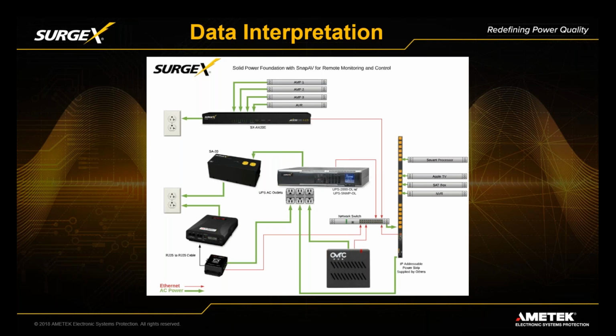And most of the summaries we give back to the integrator revolve around, let's try to address the problem globally for the whole structure, the job site, by tackling the electrical wiring, if we think that might be the root cause. And again, if it seems to be integral, then okay, let's try going over to the utility and making sure we don't have an input issue from the service.